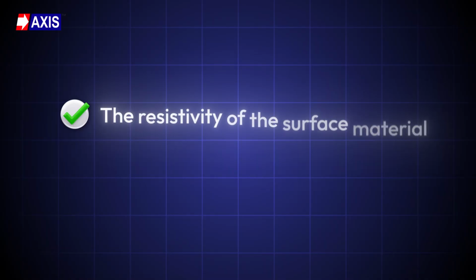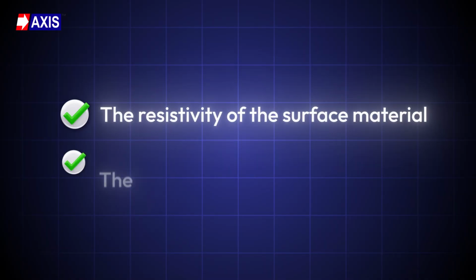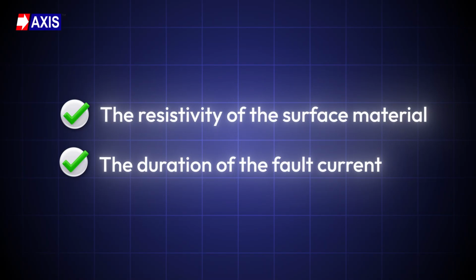Both depend on two key factors: the resistivity of the surface material and the duration of the shock current. Longer exposure and lower surface resistivity make the situation more dangerous. If touch and step potentials exceed the tolerable limits, the current passing through the body can cause an irregular heart rhythm that can be fatal. The risk is higher for touch potential because the current path runs through the chest and directly affects the heart.